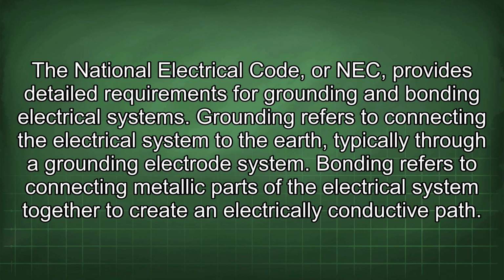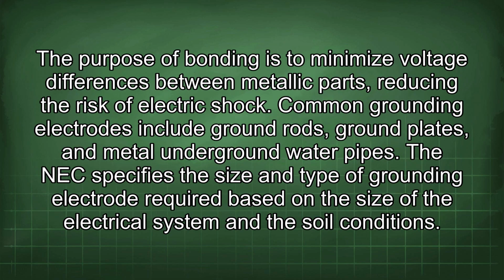The National Electrical Code, or NEC, provides detailed requirements for grounding and bonding electrical systems. Grounding refers to connecting the electrical system to the earth, typically through a grounding electrode system. Bonding refers to connecting metallic parts of the electrical system together to create an electrically conductive path. The purpose of bonding is to minimize voltage differences between metallic parts, reducing the risk of electric shock. Common grounding electrodes include ground rods, ground plates, and metal underground water pipes.